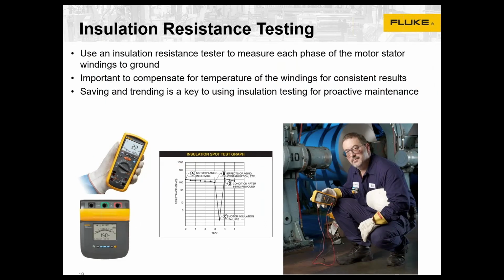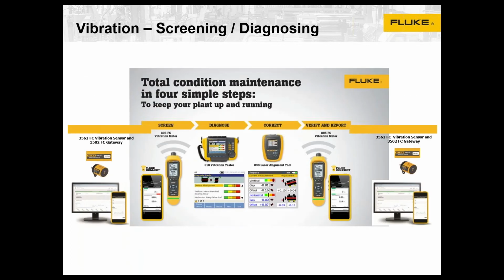Insulation resistance testing, another great way to troubleshoot motors that are overheating, tripping breakers, but you can use it proactively as well to trend insulation resistance over time. Once that starts to drop off, that might be a trigger to not wait for downtime, but to schedule maintenance, rewind, replacement, whatever that might be. So you can save and trend those readings as well. Let's take more of a look at vibration screening and diagnosing.